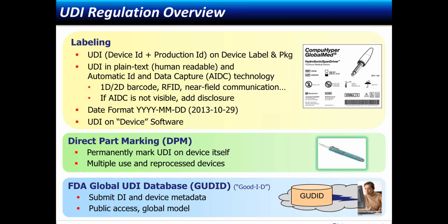This is an area where the intent is to permanently mark on the device itself. The UDI includes both the device ID and the production ID. In the event that this particular product had been separated from the package and also the label. So the example there of a scalpel, this being a multiple use and reprocessed device, most likely the label for this particular device had long disappeared, and through the course of reprocessing, sterilization, and so on, all that is gone. So in this case, the UDI must be permanently marked on the device itself.